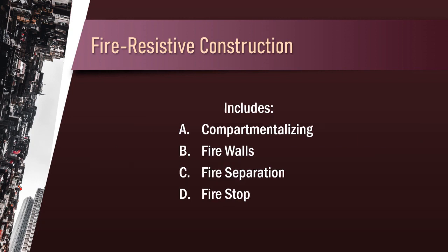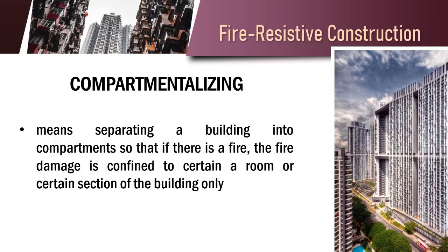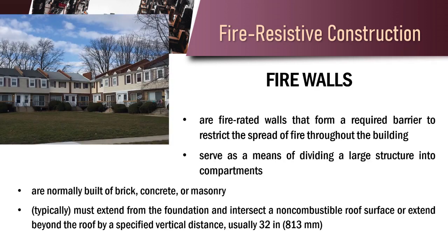Fire-resistive construction includes compartmentalizing, fire walls, fire separation, and fire stop. Compartmentalizing means separating a building into compartments so that if there is a fire, the fire damage is confined to a certain room or certain section of the building only. Fire walls are fire-rated walls that form a required barrier to restrict the spread of fire throughout the building. It serves as a means of dividing a large structure into compartments. They are normally built of brick, concrete, or masonry. Typically, it must extend from the foundation and intersect a non-combustible roof surface or extend beyond the roof by a specified vertical distance, usually 32 inches or 813 millimeters.